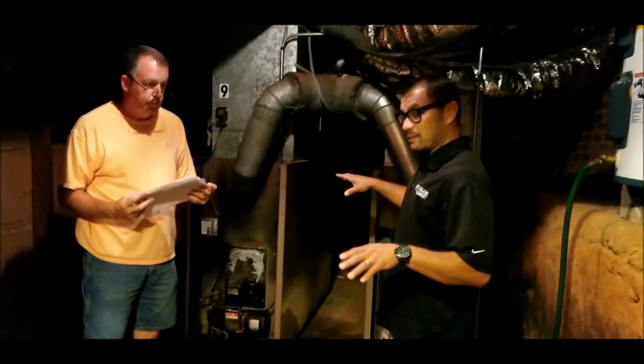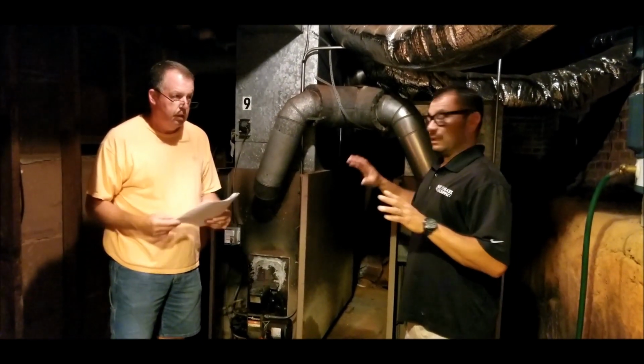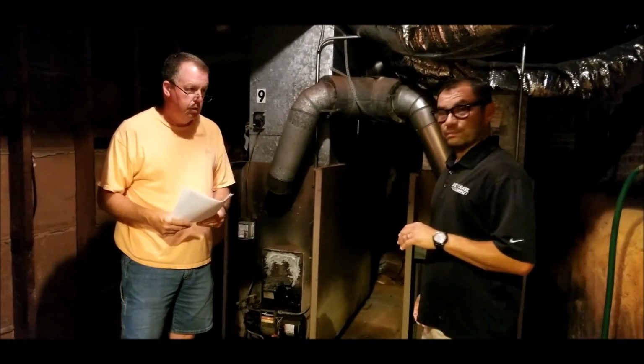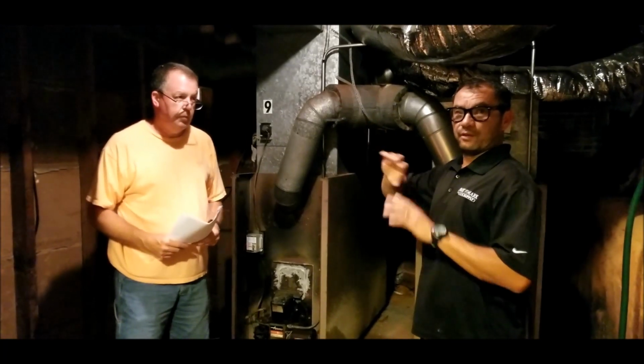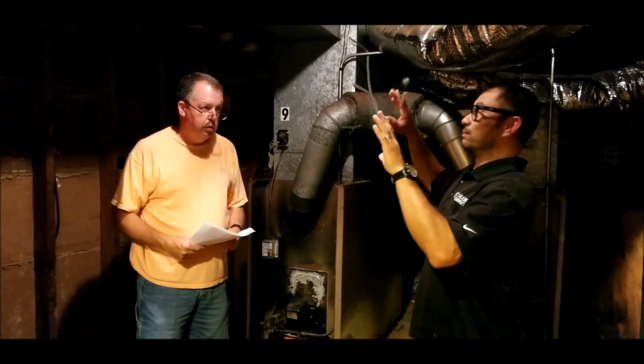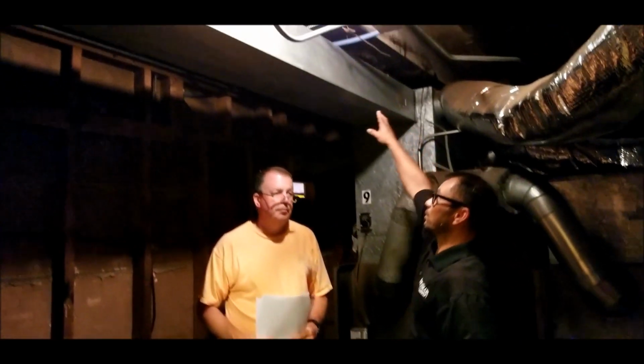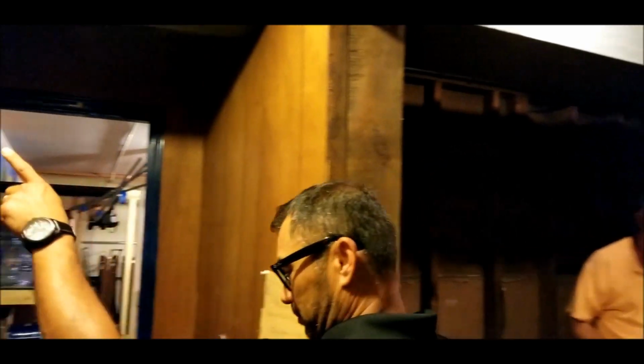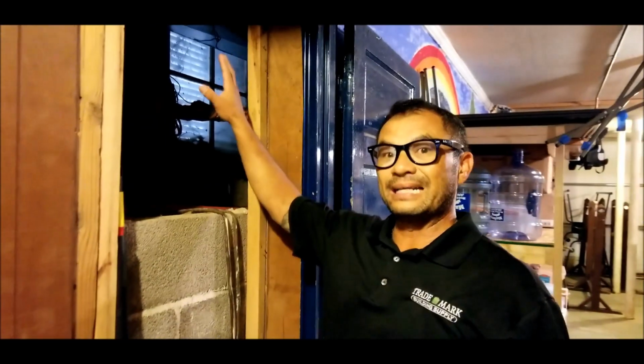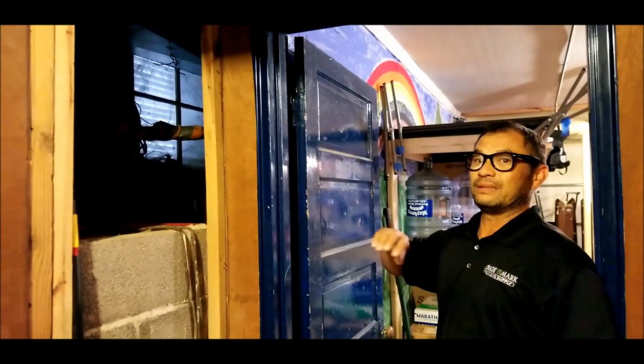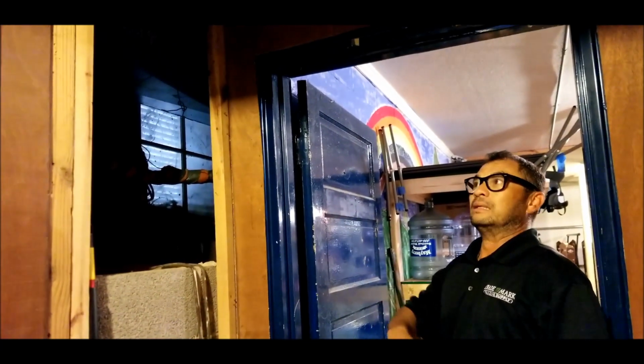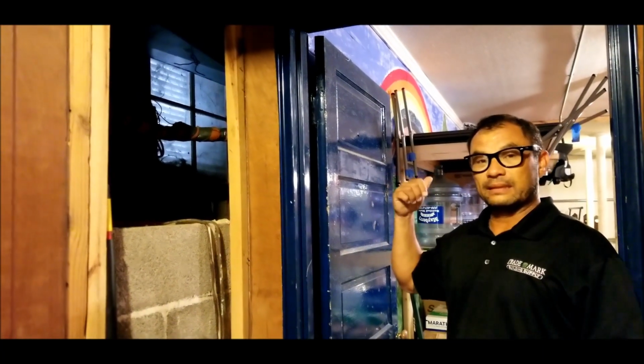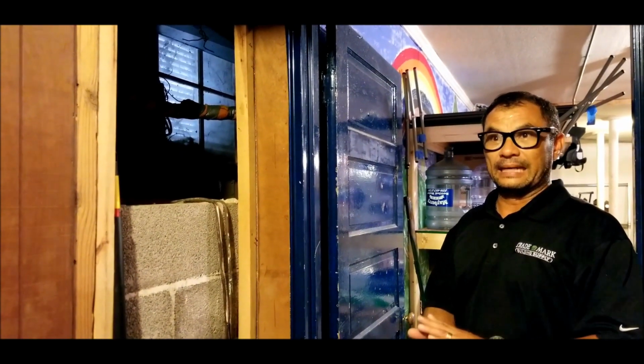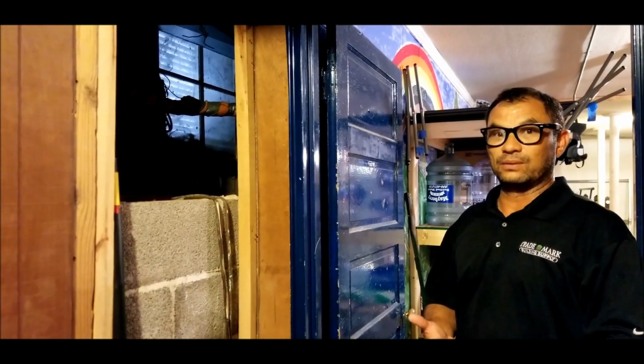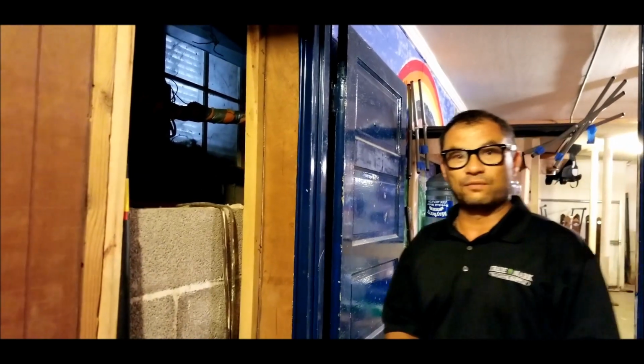We feel the best option for the old sanctuary is to get a heat pump, do away with this old heating system, and just install a heat pump in the attic. There's already a heat pump up there, actually 2. But the issue is that if we put the heat pumps down here, the ductwork running behind the unit and down both sides of the old sanctuary is not insulated. All that old ductwork would have to be taken out, and we feel it would be extremely expensive. That's why we feel going up through the attic with the existing heat pump ductwork makes more sense - we'll talk about that unit next. It died probably 10 years ago, and I think that'll be our next adventure after this one.